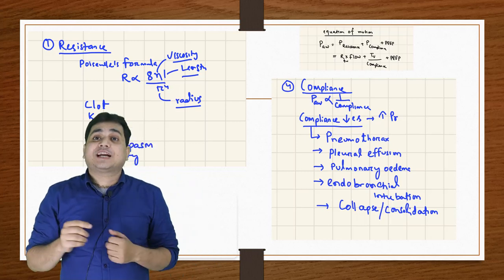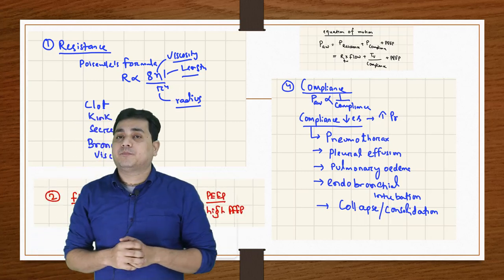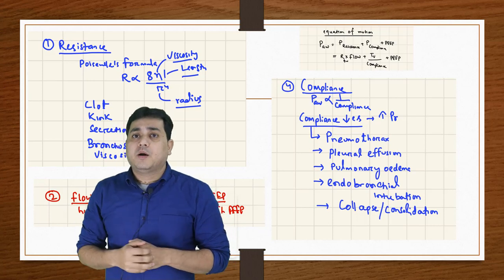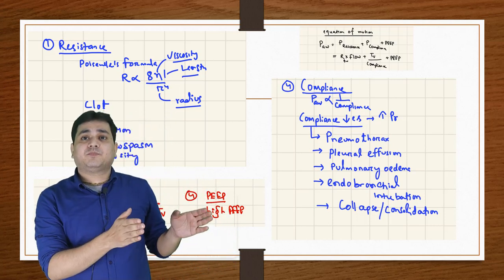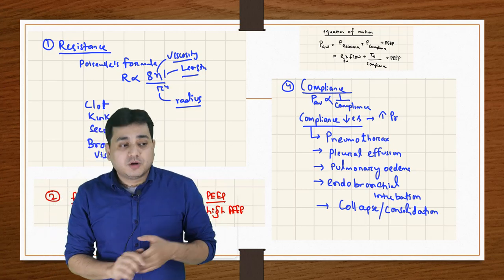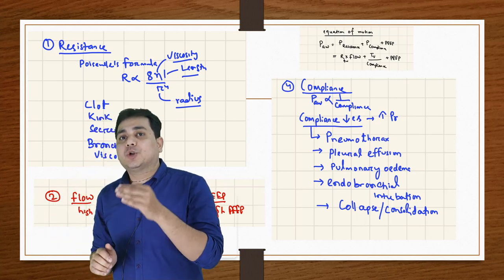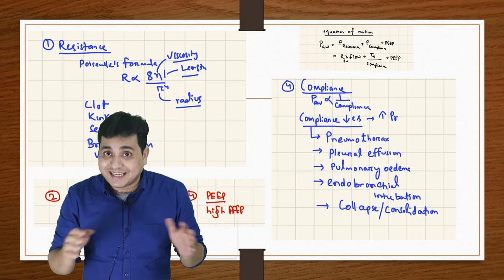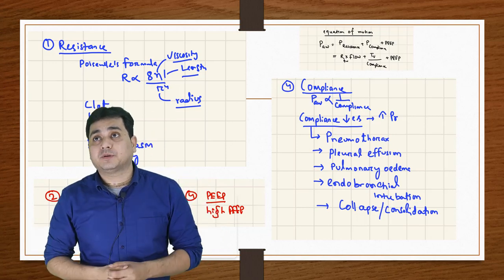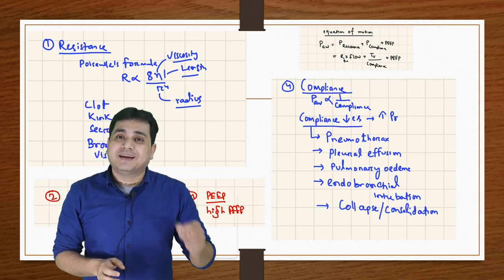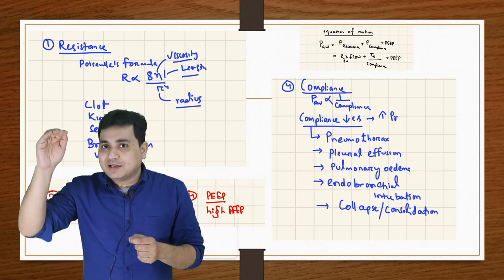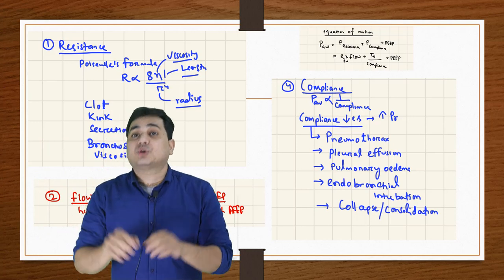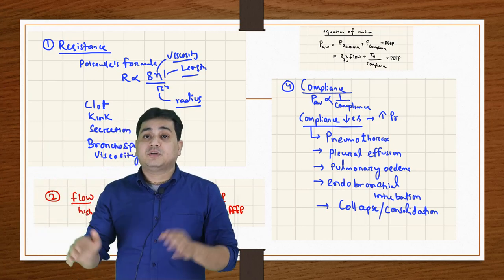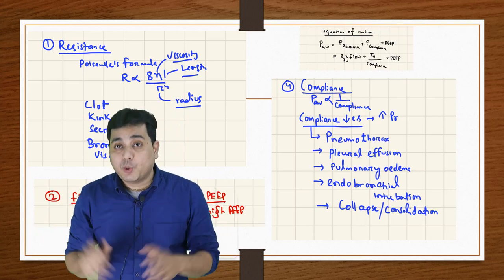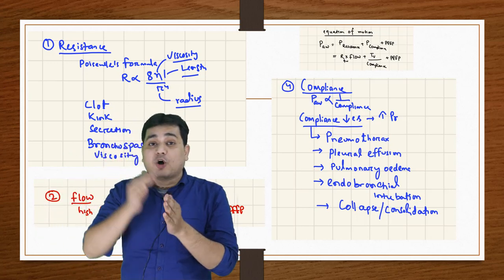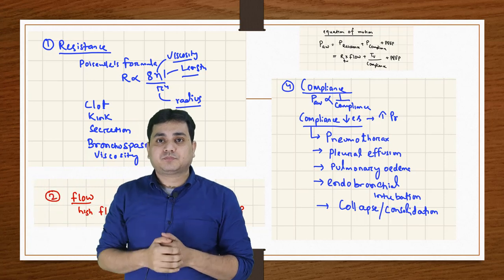Of course, it is also directly proportional to the tidal volume, to the flow, to the PEEP. But when you set a patient on a ventilator, these things are constant. So these things cannot increase the peak airway pressure suddenly. However, they can make the peak airway pressure look bigger. So do not tamper with them in the beginning. You can do it as a temporizing measure to keep the peak airway pressure a little bit low, but this is not a solution. Decreasing flow or decreasing tidal volume may not always be the solution. So we have to find out what the resistance problem or compliance problem of my patient is.